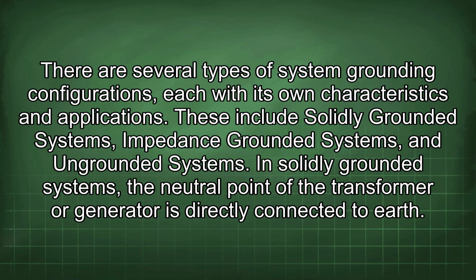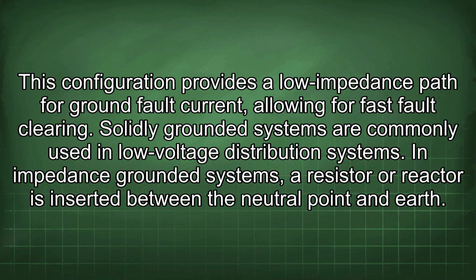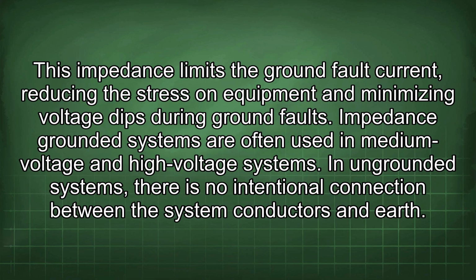There are several types of system grounding configurations, each with its own characteristics and applications. These include solidly grounded systems, impedance grounded systems, and ungrounded systems. In solidly grounded systems, the neutral point of the transformer or generator is directly connected to earth. This configuration provides a low impedance path for ground fault current, allowing for fast fault clearing. Solidly grounded systems are commonly used in low voltage distribution systems. In impedance grounded systems, a resistor or reactor is inserted between the neutral point and earth. This impedance limits the ground fault current, reducing the stress on equipment and minimizing voltage dips during ground faults. Impedance grounded systems are often used in medium voltage and high voltage systems.